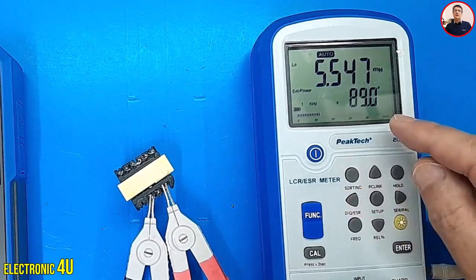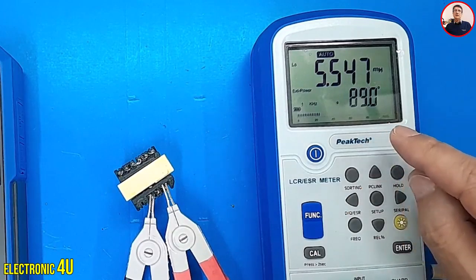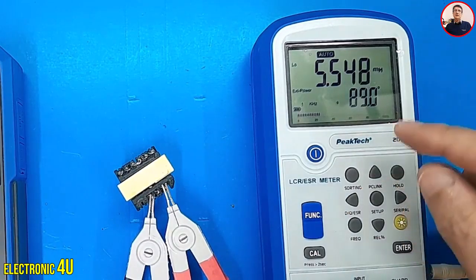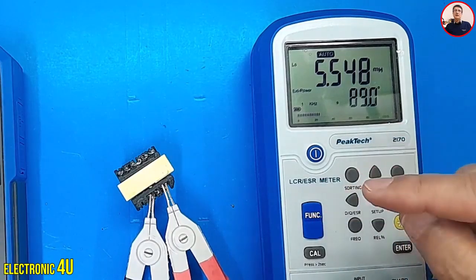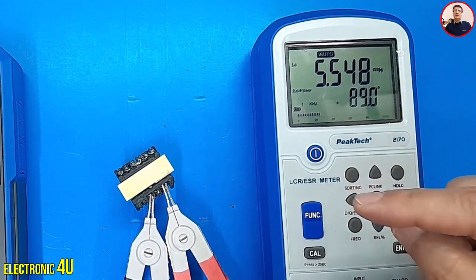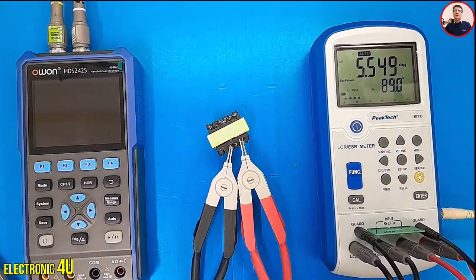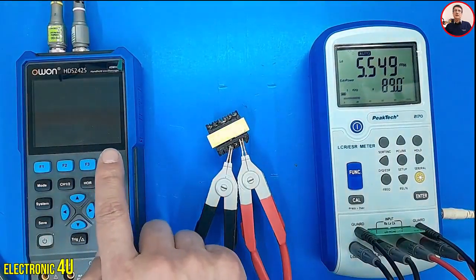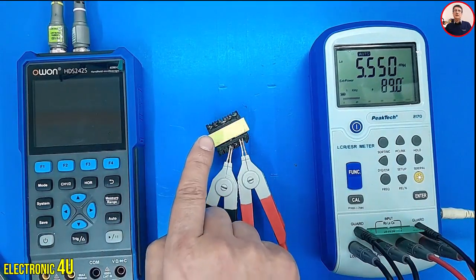What matters to us is the phase angle. This number should be close to plus 90 degrees. When the LCR meter is connected to the transformer, it injects a sine signal into the inductor, causing magnetic induction in the secondary winding.